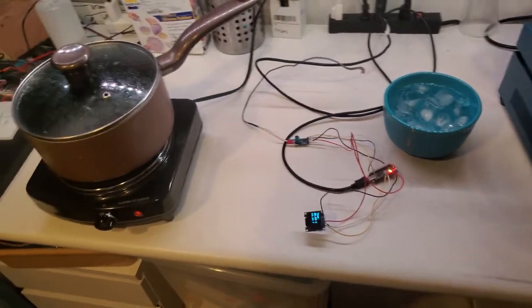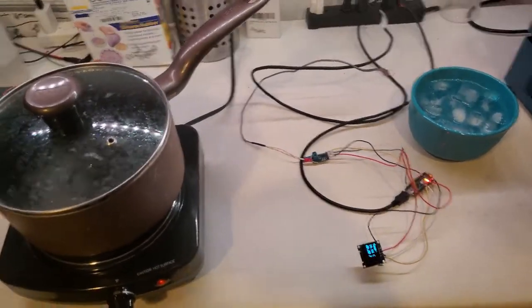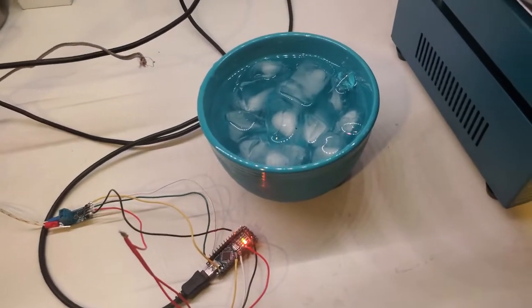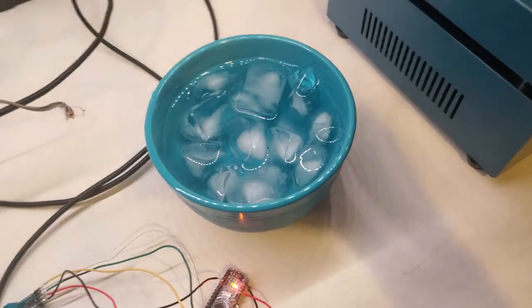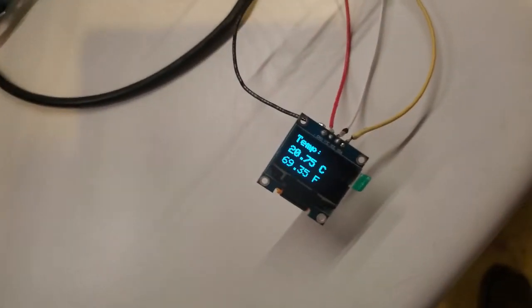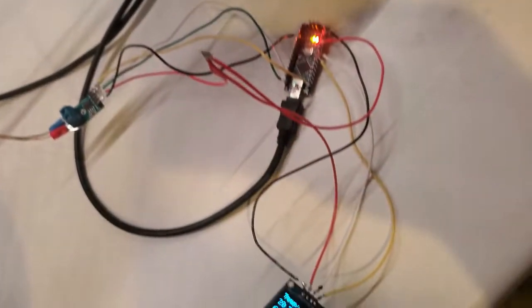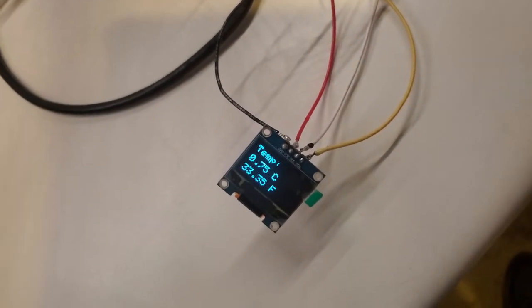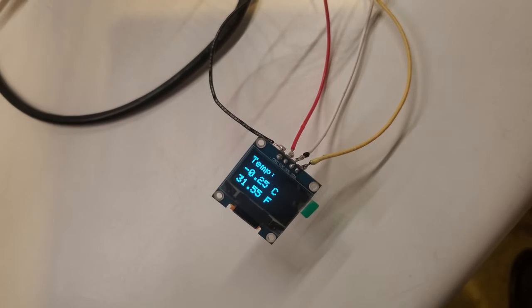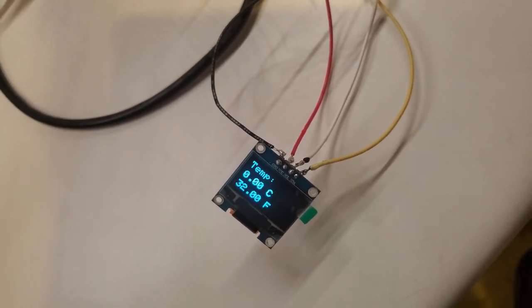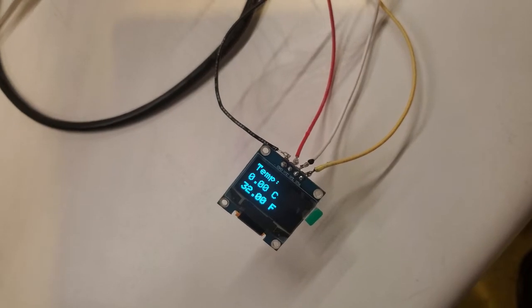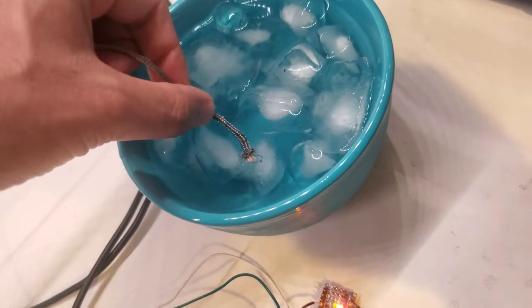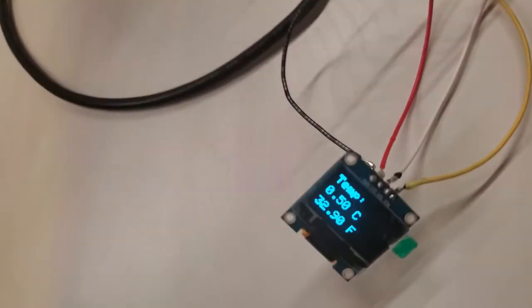Okay, so now it's time to calibrate the thermocouple, and this is very easy. You just need a pot of boiling water and a bowl or a cup filled with ice and some water. Right now it's reading about 21 degrees Celsius. If we put it in the freezing cold water, it should go down to about zero degrees Celsius. This one has been previously calibrated, so it's actually right on the money there—zero degrees Celsius. Just make sure the thermocouple is submerged well and touching the ice is good.